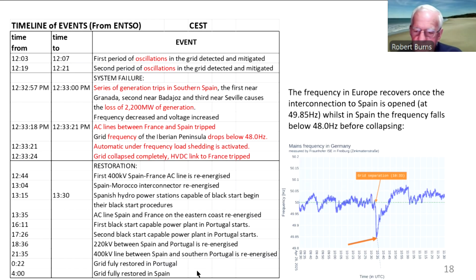49.85 hertz, that's not a huge deviation, but the interconnector with France opened. And of course, Europe, measured at Germany, recovered. Its frequency went back up around 50 hertz again. Whereas Spain went down the gurgler at 48 hertz and then collapsed. 48 hertz seems to be the frequency at which automatic under-frequency load shedding is activated. We have that here. It's sort of a last-ditch resort.